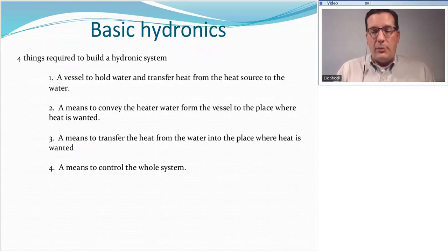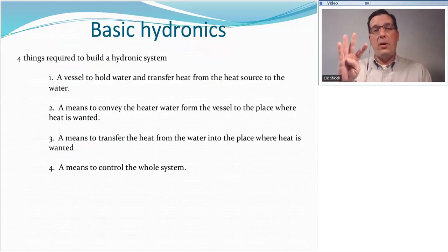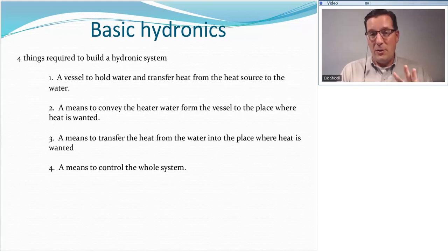So that covers our pros and cons between forced air versus hydronics. And as you can see, there's really no clear winner. There's advantages and disadvantages on both sides. So you just need to be aware of what the limitations are and what the characteristics are. That's it. When we're talking about basics, there's only four parts to every hydronic system, and I like to break everything down to as simple as it can possibly be, right? You probably picked up on that when I told you about the water bottle. When we have an active hydronic system, there's really only four parts to it. As complicated as all these systems can be, it always breaks down to there's still only four parts.